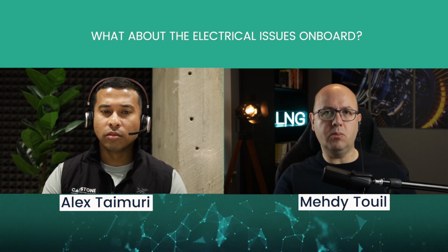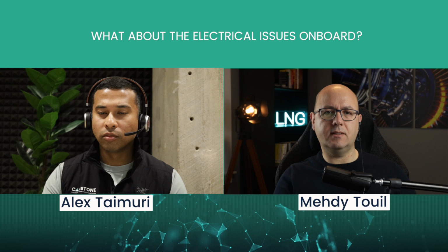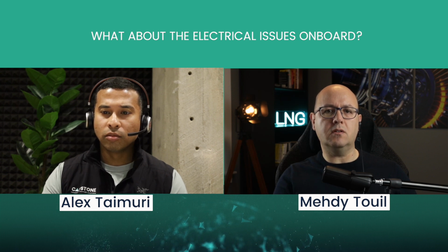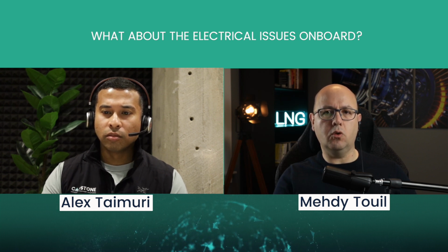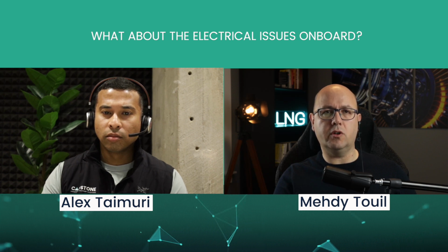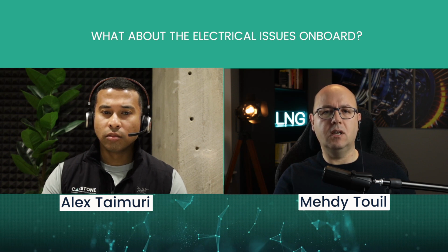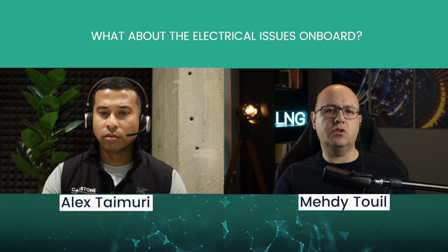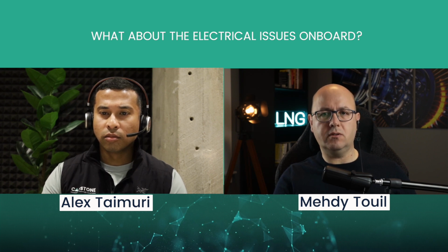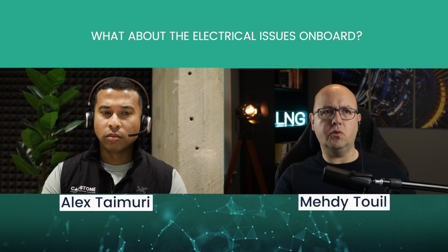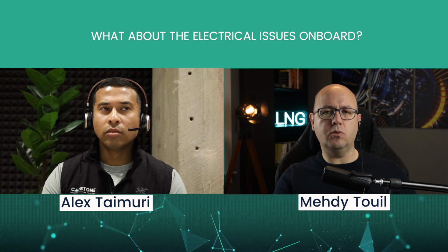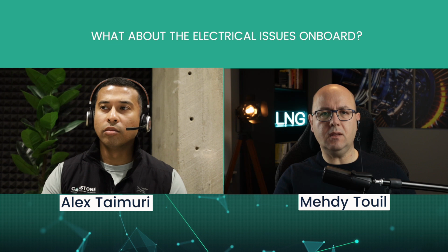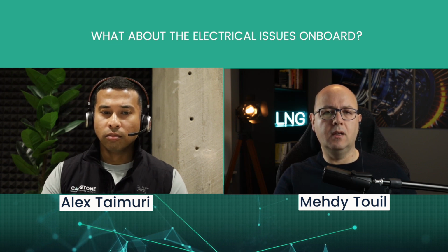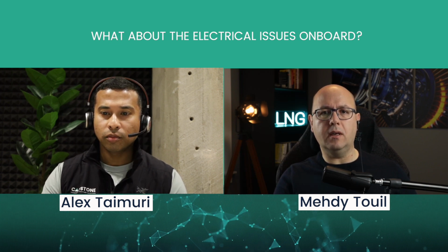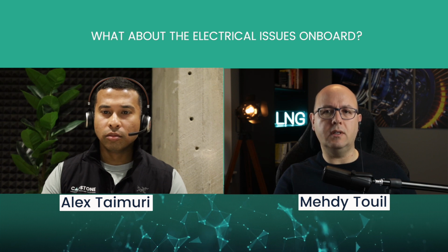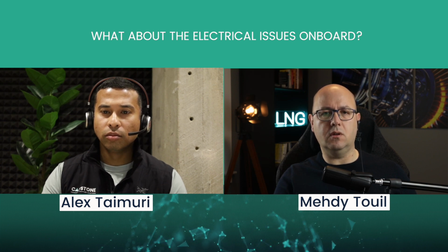With no gas available to feed the boilers and generate steam, Prelude experienced a total loss of power, followed by the failure to restore it despite multiple attempts over several days to start the 3 emergency diesel generators that have a combined output of 23 megawatts. This is for essential power. The staff was evacuated by helicopters and boats because of the degraded living conditions on board.